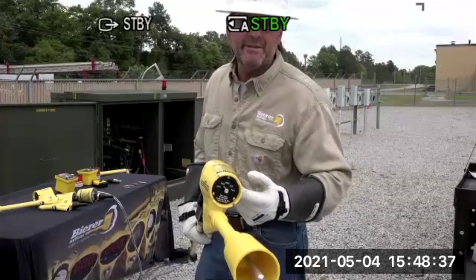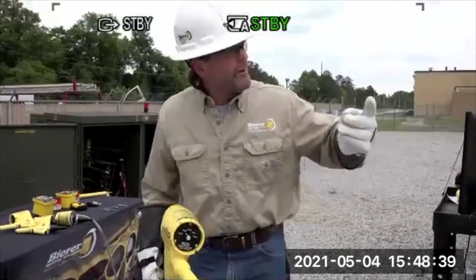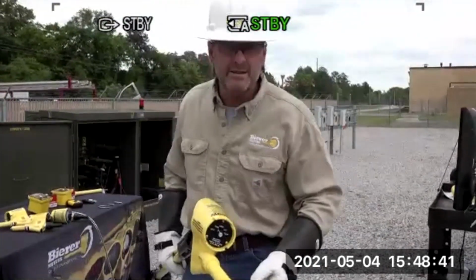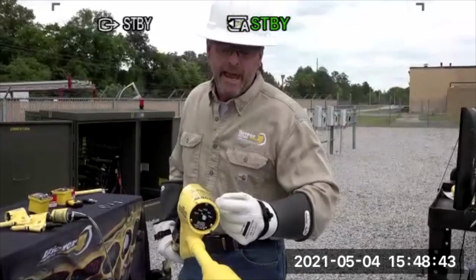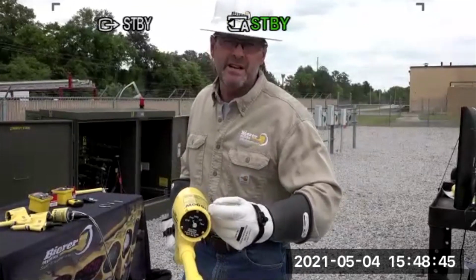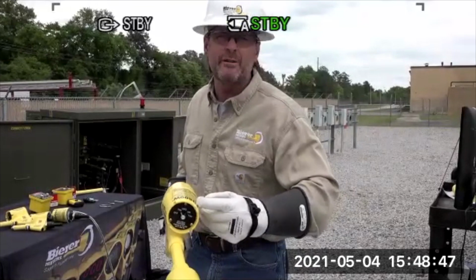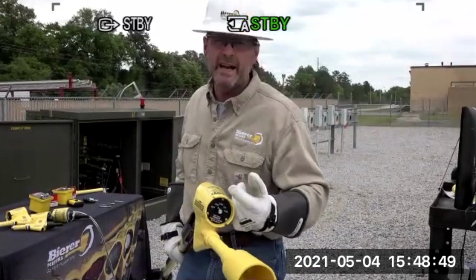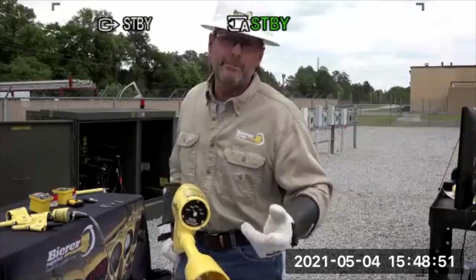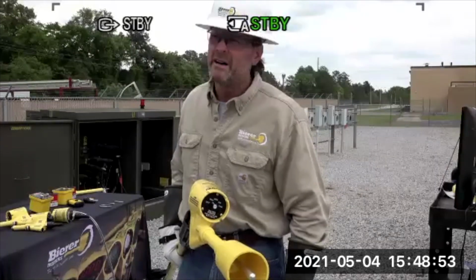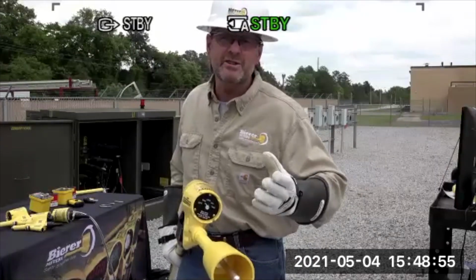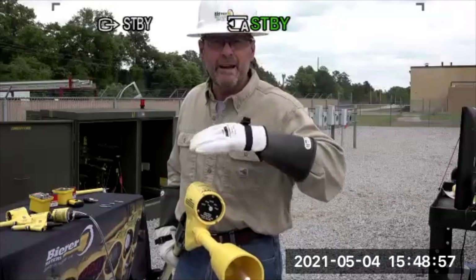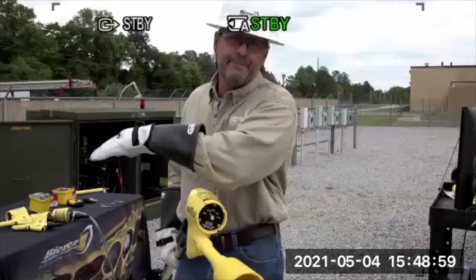And when you're looking at the phasing with this tool, we have a referenced blue phase or C phase. When you touch a conductor with this tool, it doesn't care if it's on the high side, the low side, secondary, primary power, capacitive test point, hot bushing. It doesn't care. It's just looking at the phase angle that's generated from the generation plant. That's all it cares about.